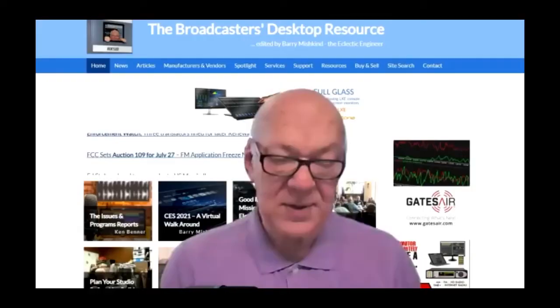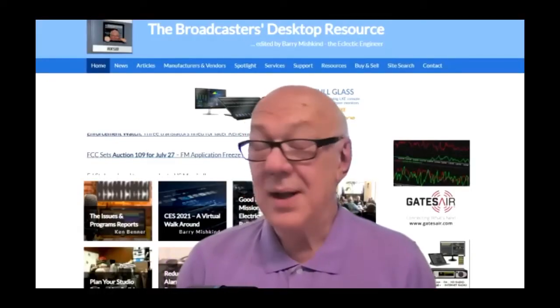So review your grounding situation as often as you can and make sure that it is resilient and can stand the high frequencies that do most of the damage. Most surge protectors can't even catch up with the high frequencies when they come in on a lightning strike. Those are good points, thank you, Tom.